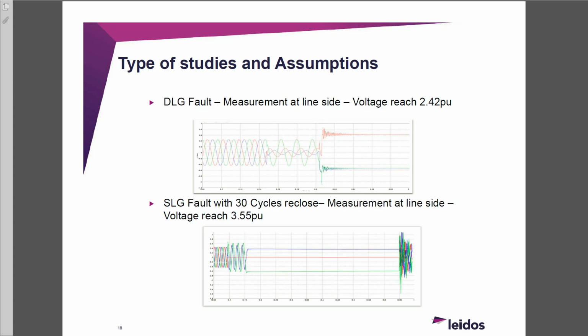You don't have surge arresters. Well, exactly, those would be kind of a mitigation there, like pre-insertion, we'll talk about that. So first we did without — that's another thing we did for our clients, because they're big clients, IOUs, and they don't want to test every single line. So we said, let's grab your longest line that gives you the worst case. Let's not use surge arrestors, let's not use pre-insertion. Nothing. Let's just see how bad it is, and then we start doing the mitigation.